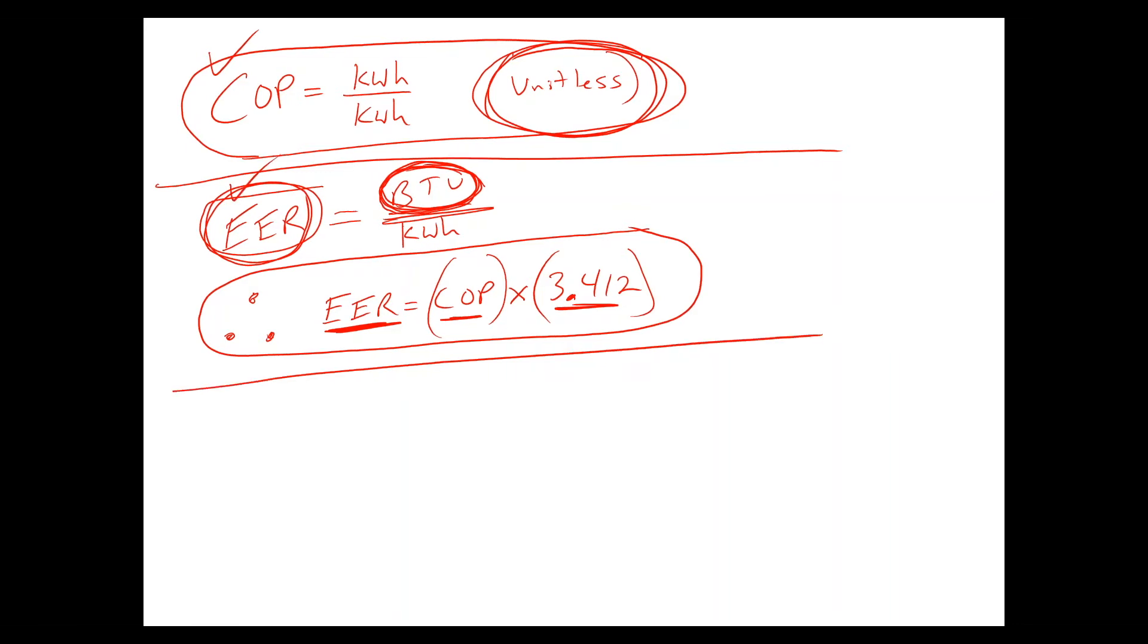One is called the seasonal energy efficiency ratio, which if you consider EER and COP, they're somewhat instantaneous. They are some measurements that are taken. Seasonal energy efficiency ratio is looking at the EER over the summer season. So they take longer measurements. They do this in a lab, they put the heat pump in the condition of summer, which is trying to cool. And the seasonal energy efficiency ratio is a good way to compare models if you need a lot of cooling.